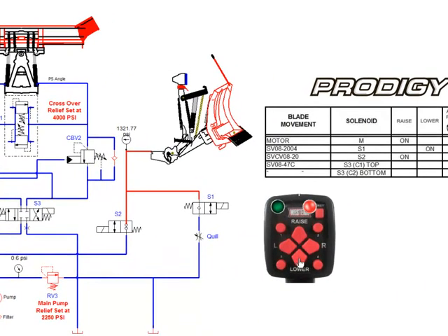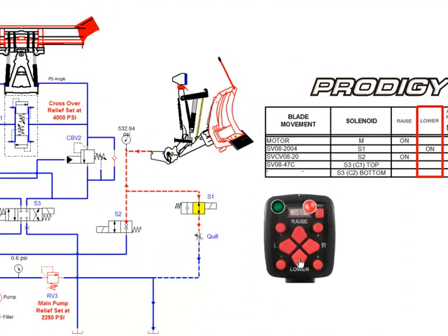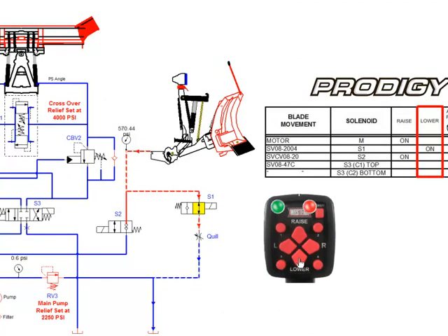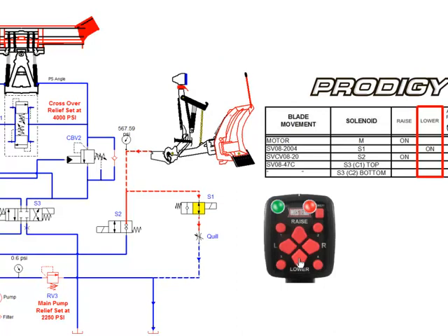Pressing the lower function will engage the S1 coil. S1 valve will shift allowing fluid to flow out of the lift ram, through S1, through the adjustable quill, and back to tank.